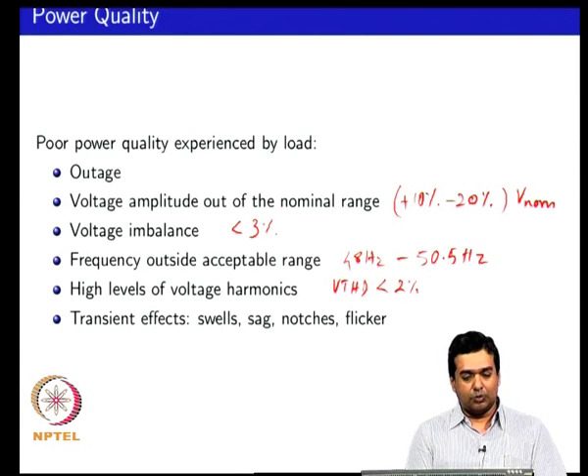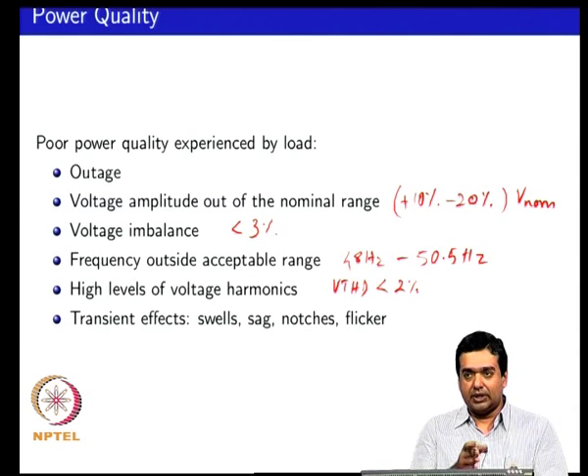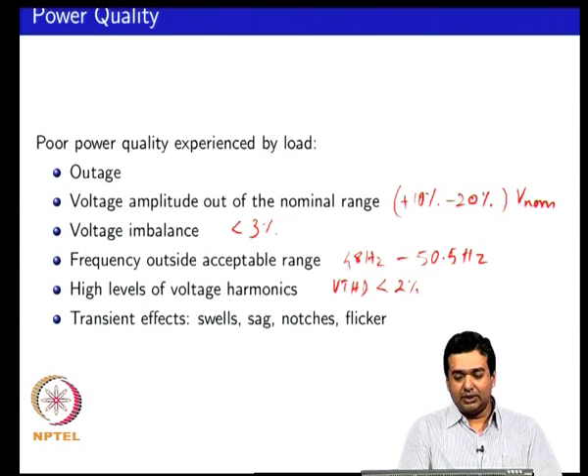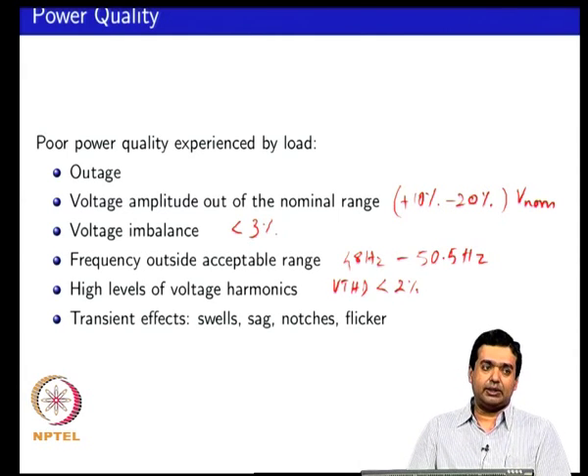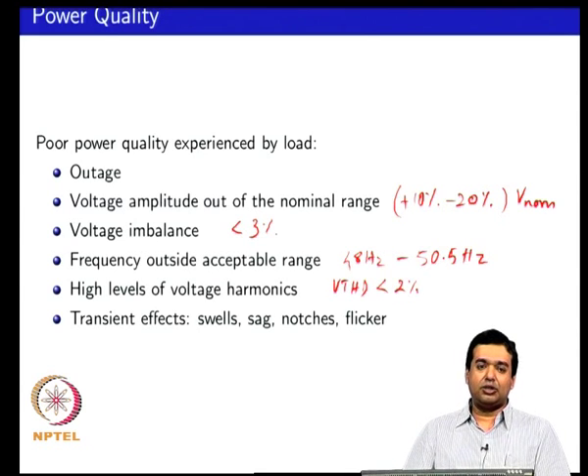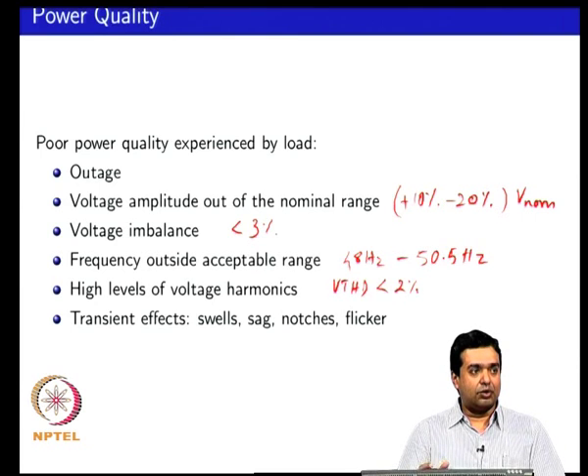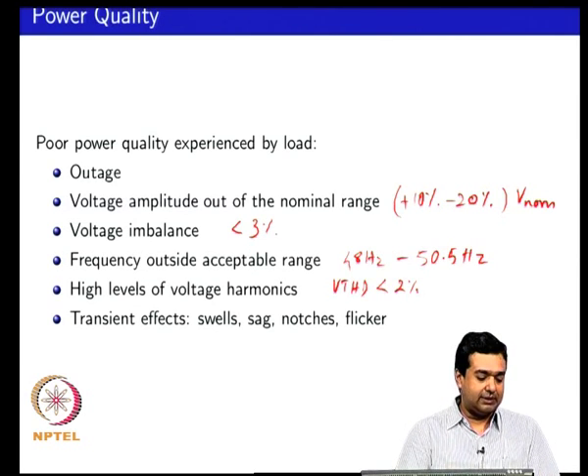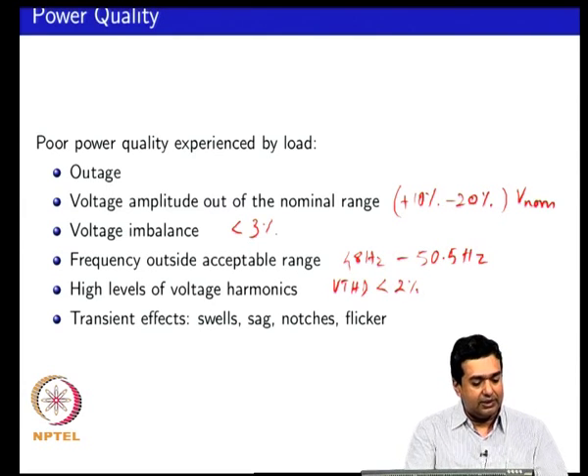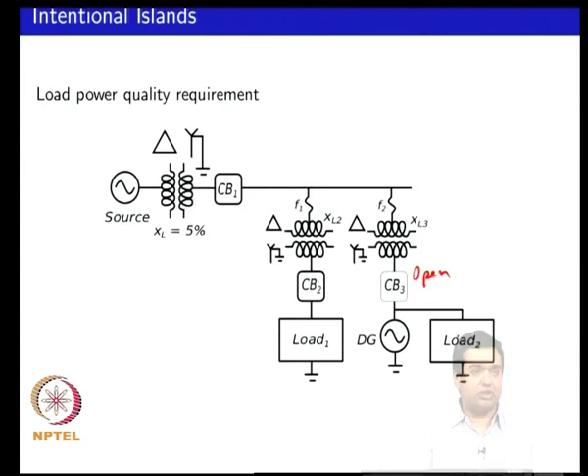You can have transient effects which also affect power quality — a short-term increase in voltage amplitude or a short-duration voltage dip, which is called a sag or a swell. You might have notches in the waveforms if you have thyristor power converters connected to your point of common coupling. You can have flicker in your load if someone is operating an electric arc welder on the same street. For many of these power quality reasons, you might want to intentionally disconnect from the grid and feed your local load from a DG.